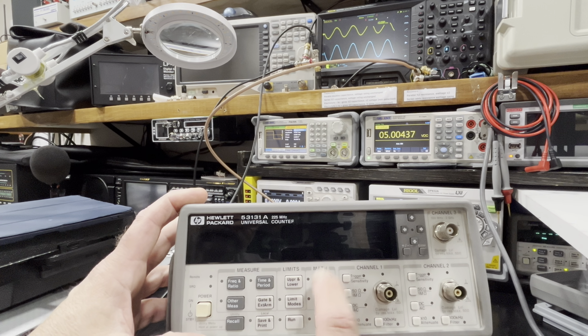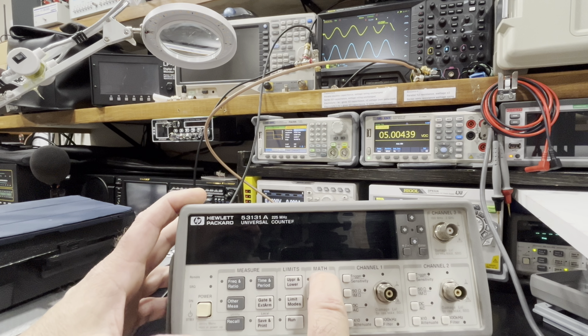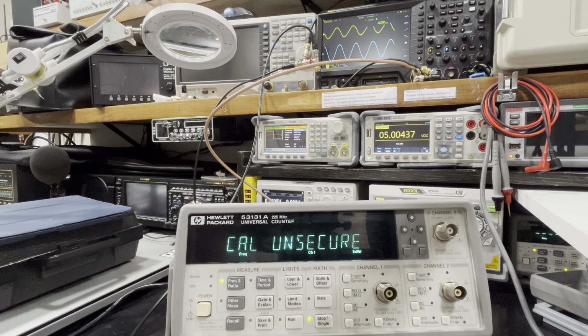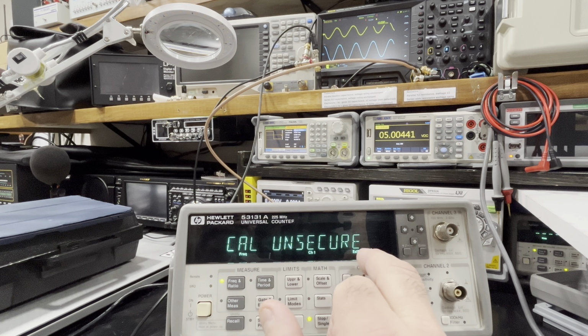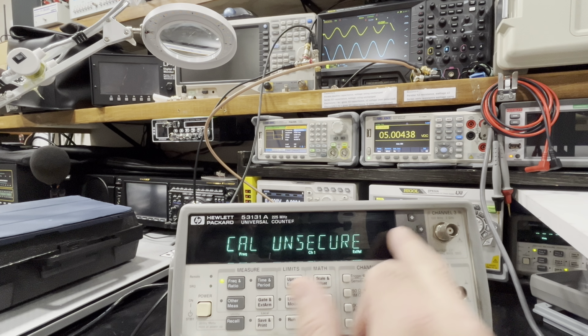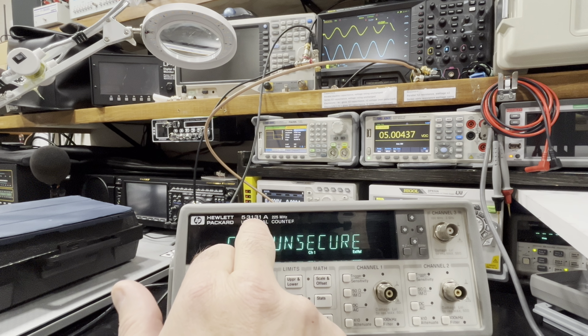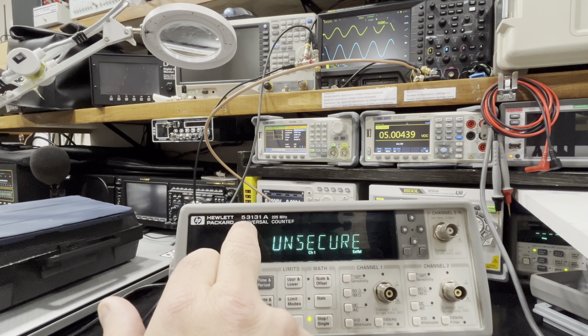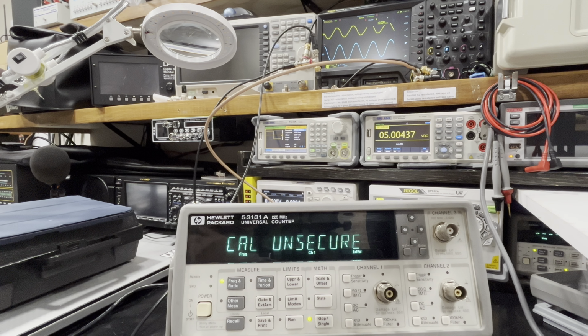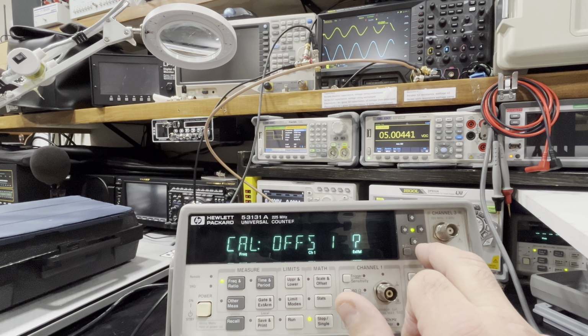So you hold in this scale offset button, gonna power it on. Cal unsecure, which means that we could go ahead with the cal. If it said cal secure on here, all you got to do is use these arrows here to type in 53131. That's the model, and it'll unsecure it. If no one's changed it, if they changed it, kind of screwed, but we're good. So you hit this again. It's going to put you in an offset. We're going to hit enter.